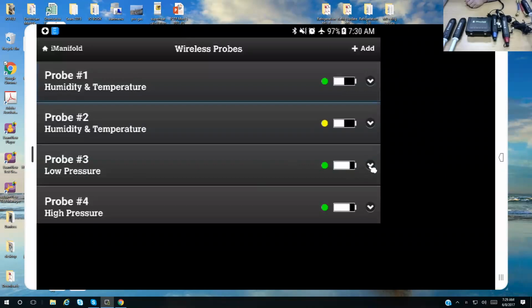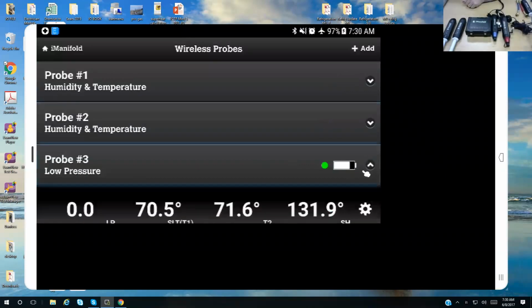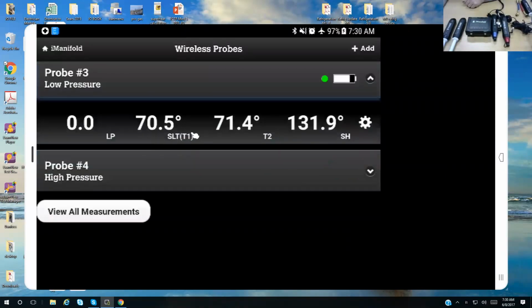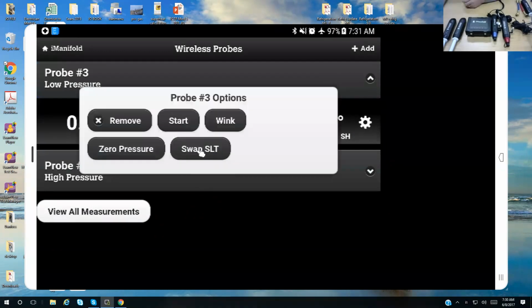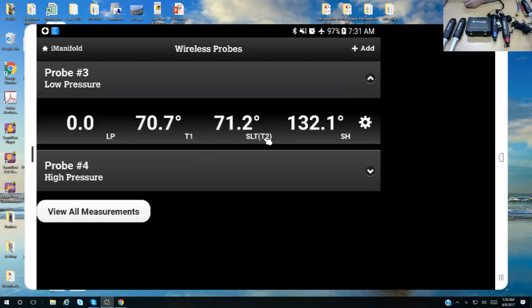And then on the pressure probes, this is where I have my thermometers plugged in. We have T1 and T2. You see T1 here is already mapped to the suction line, and T2 is open to whatever we want to use it for. If I wanted to switch these around, for example, move the suction line over to T2, I would do it from this menu. Swap suction line temperature right here, and it will move the suction line over to T2.